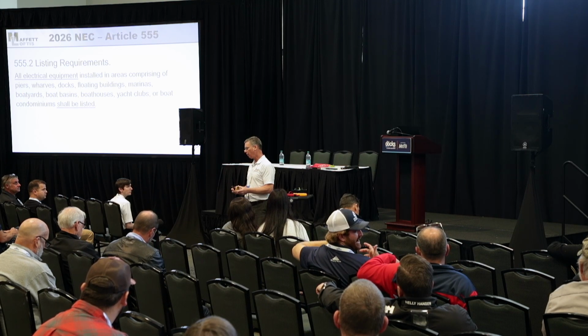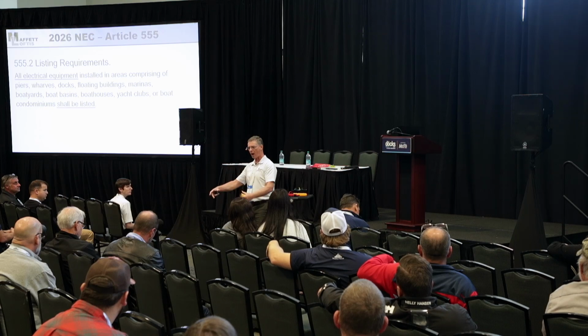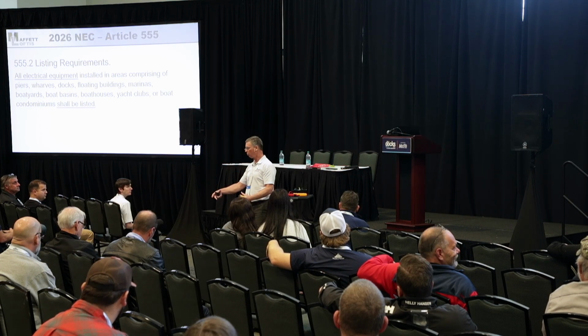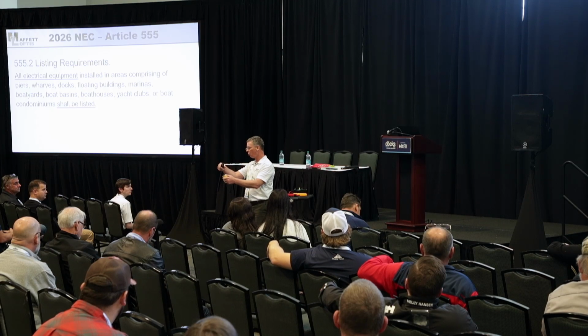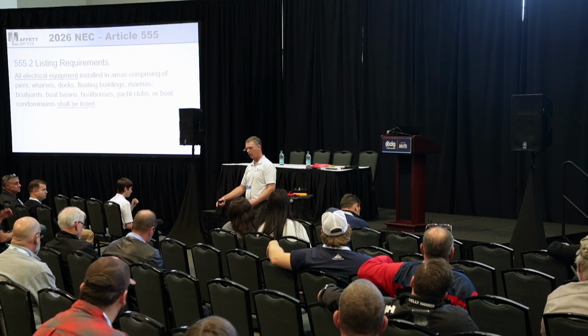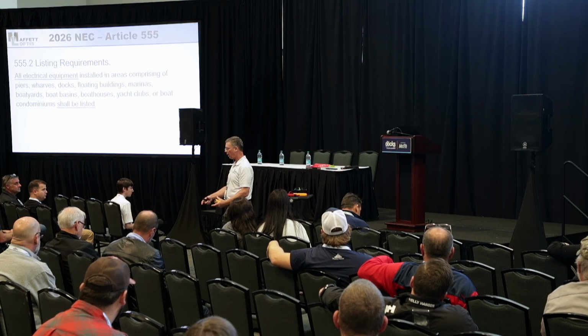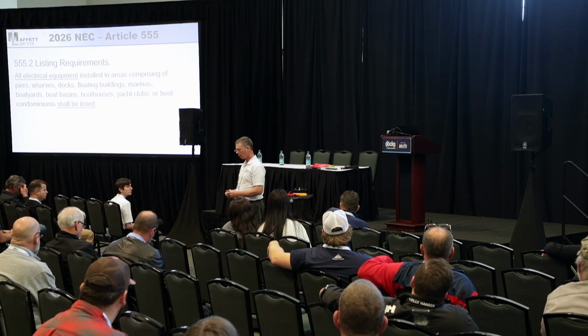A lot of these don't make sense, especially going from a 50 amp down to a Y30. Have you seen those? What's the problem? You have a 50 amp overcurrent protection feeding two 30 amp receptacles, so you could be pulling 40, 45, 48 amps on a 30 amp, number 10 wire. That's a fire hazard because it will overheat and eventually melt down. So those are not listed.